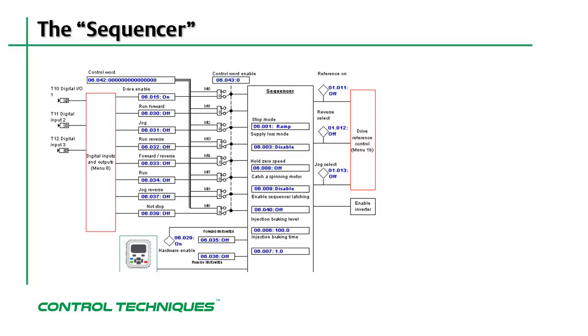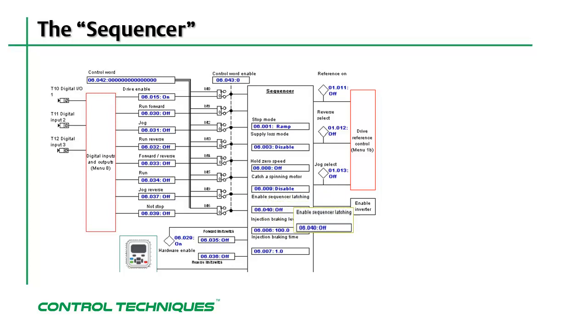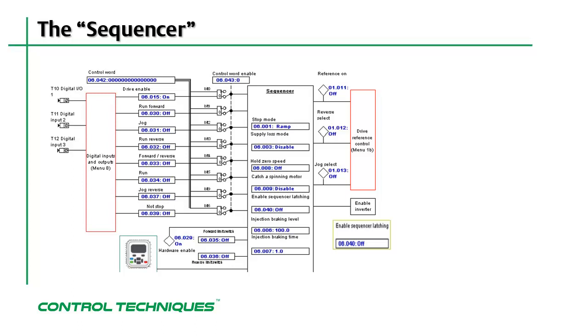Sequencer destinations like run forward can also be configured to be latched using menu 6, parameter number 40. Latching means that once the source for the sequencer destination becomes true, like a digital input coming on, the sequencer function that is associated with the digital input will remain active even if the source changes state.